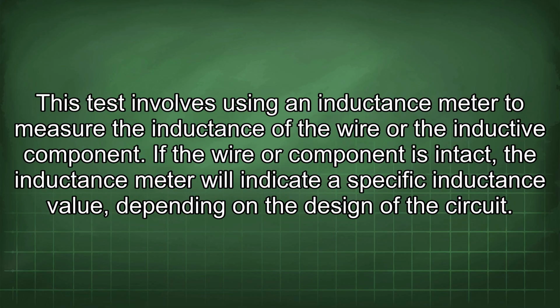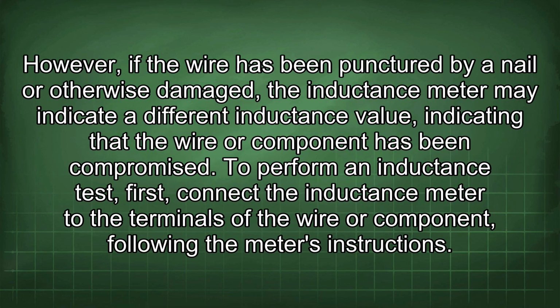This test involves using an inductance meter to measure the inductance of the wire or the inductive component. If the wire or component is intact, the inductance meter will indicate a specific inductance value, depending on the design of the circuit. However, if the wire has been punctured by a nail or otherwise damaged, the inductance meter may indicate a different inductance value, indicating that the wire or component has been compromised.